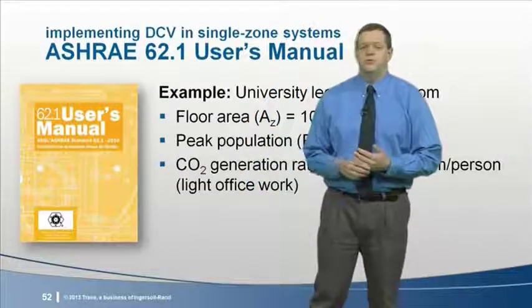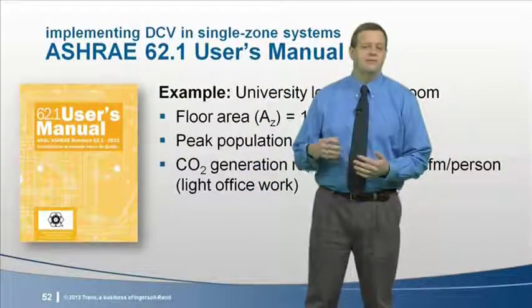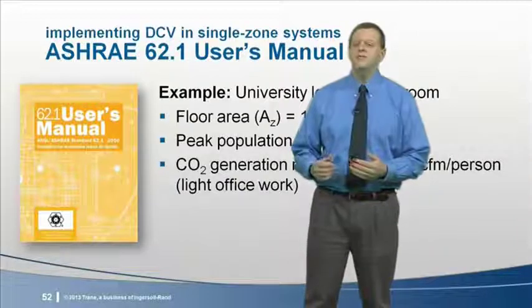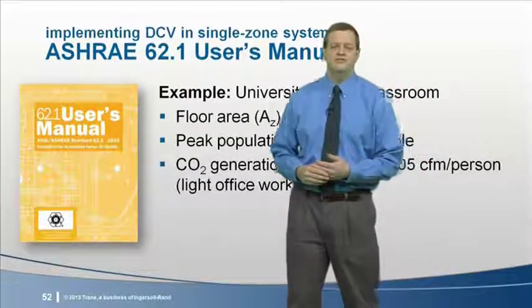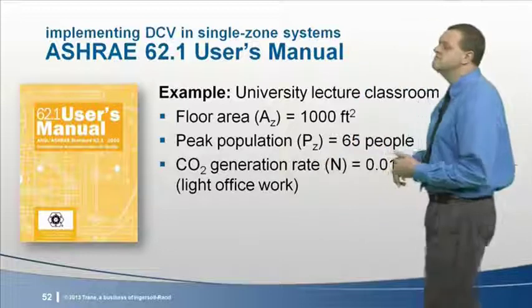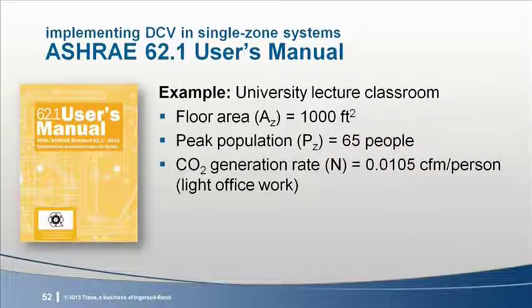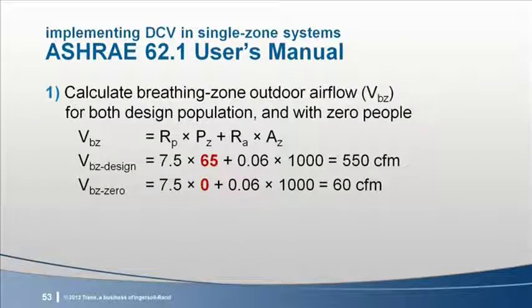Now the Standard 62.1 User's Manual describes a proportional control sequence that can be used to implement demand control ventilation in a single zone system. To explain it, let's use an example 1,000 square foot lecture classroom with a peak population of 65 occupants and a CO2 generation rate that's typical for people doing light office work. The first step of the process is to calculate the outdoor airflow required at both peak population and with 0 people.